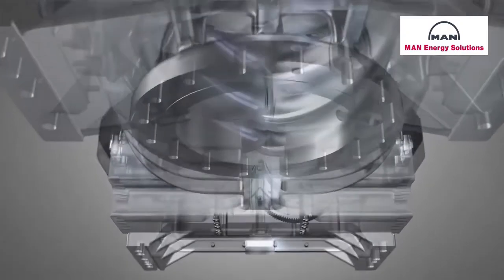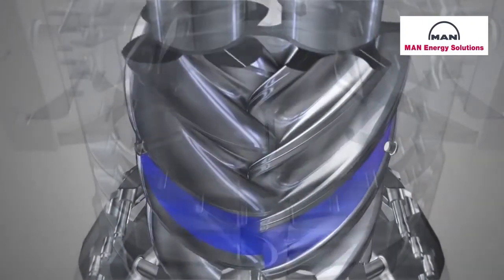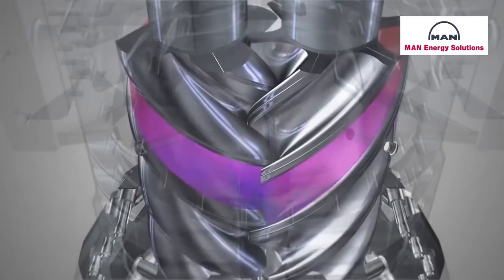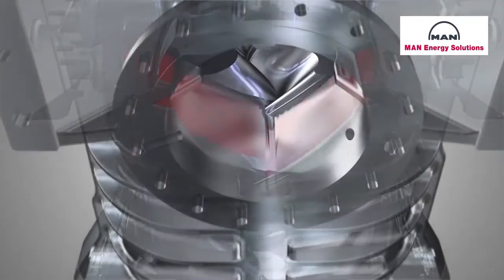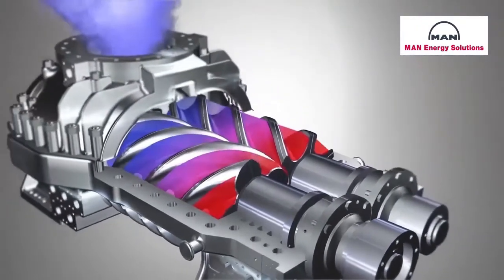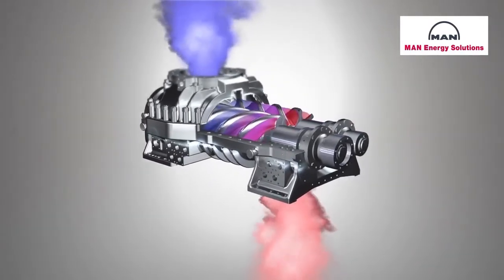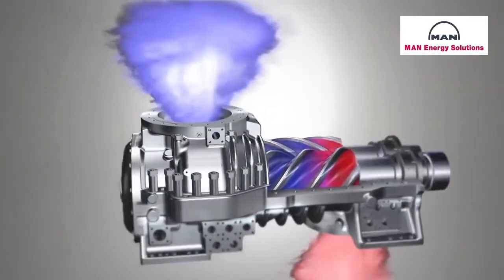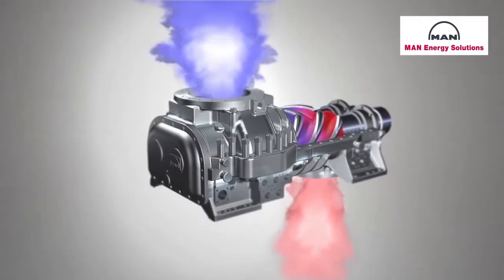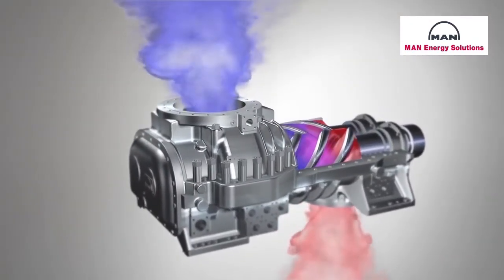Let's view the process again, this time from below. Once the gas is compressed, the chamber reaches another port connected to a discharge nozzle, and the gas flows out. In fact, all the chambers between the two rotors are being filled and emptied continuously, meaning that with a screw compressor, the compression process is more or less ongoing.